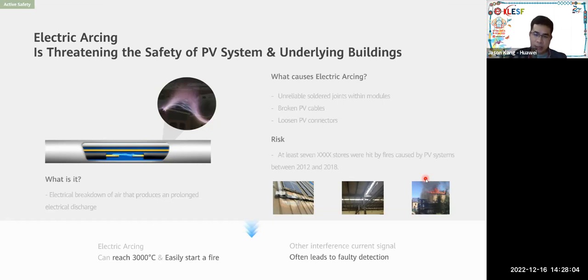So when an arc happens in an AC system, the arc can be extinguished rather naturally. And furthermore, if you look at it on a global scale, or the global IEC standards and so on, the AC system in regards to protection is pretty mature. You have earth fault protection, overcurrent protection, SPDs, and so on.